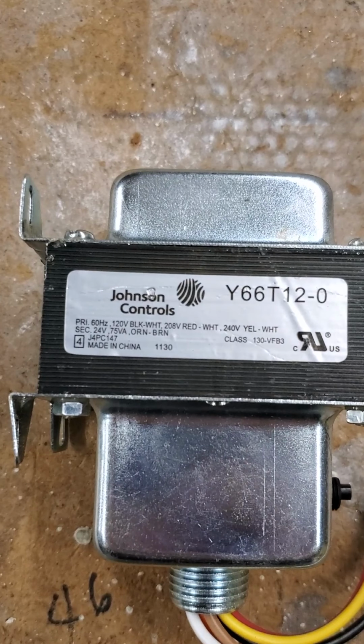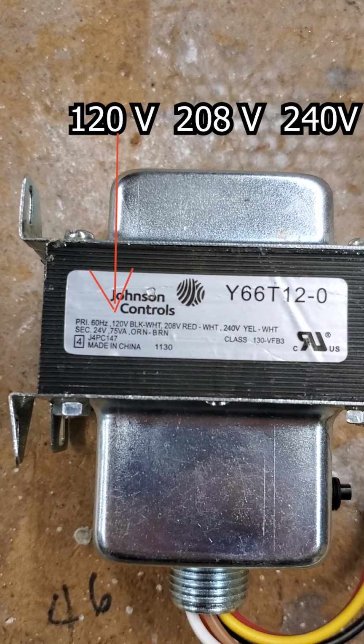All right, so this shows the wiring for the entire transformer. This one has a possibility of being hooked up to 3 different high voltage inputs and then putting out 24 volts on the other side. If you see here, we can get 120 volts, 208 volts, or 240 volts.